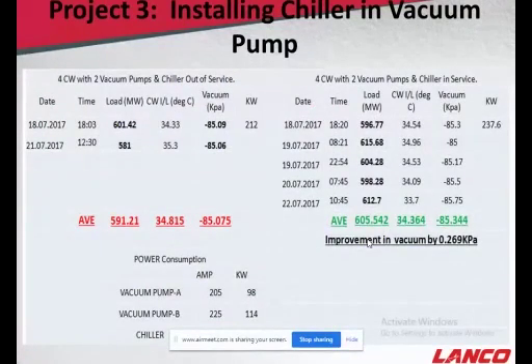These are some data from the running vacuum pump for the load and vacuum improvement. There is a slight increment in the power consumption due to the chiller, but it was well compensated by the improvement in the vacuum of 0.269 kPa under two different conditions: without chiller and with chiller, with the vacuum pump running. So the main objective was to see how many days we have to run this and in what minimum time we can achieve the payback.